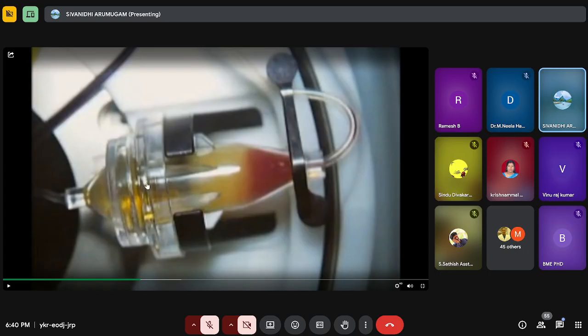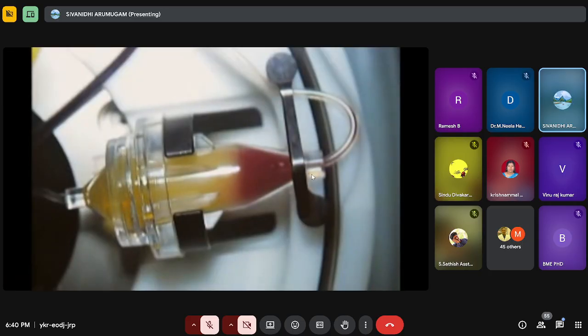For example, this cone is called a leukoreduction cone. Leukoreduction means it removes WBC and gives only platelets and plasma. This is a big topic, so I'm not going to explain it fully. You can see this cone will separate our buffy coat into only platelets. The WBC will deposit in this cone only. It won't be transfused to the bag. The target cells are held in the chamber during a secondary separation step. The platelets are then pumped back to the patient.